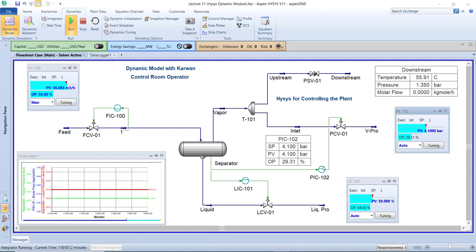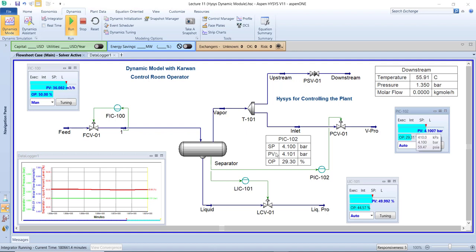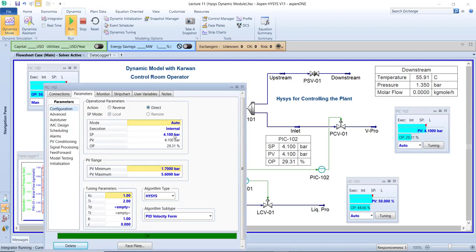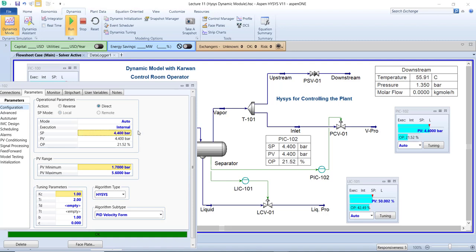The set point of the PIC is now 4.1. I want to increase more because the process is still okay — the pressure has increased but as I said we have several parameters and equipment in the plant and I'm not feeling the pressure is increased because there is no alarm yet. I want to increase to 4.2, then 4.3 — the PV is following to 4.3, and the output manipulator of the valve is decreasing because we want to increase the separator pressure. Let me change to 4.4, 4.5.